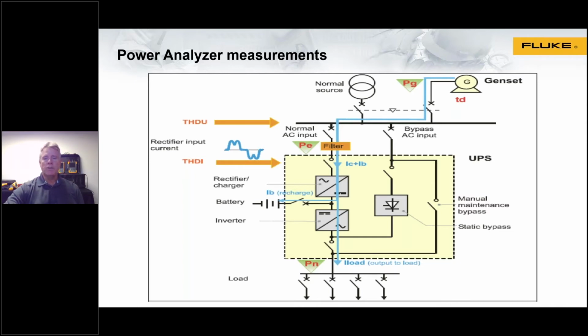into two stages. One would be pre-installation, so testing prior to connecting your critical loads. What we would be using to simulate the load here would be load banks, either resistive or a combination of resistive and inductive, or resistive and capacitive to simulate different types of power factor that might be representative of the loads. So for pre-installation, keep in mind that we're using load banks.